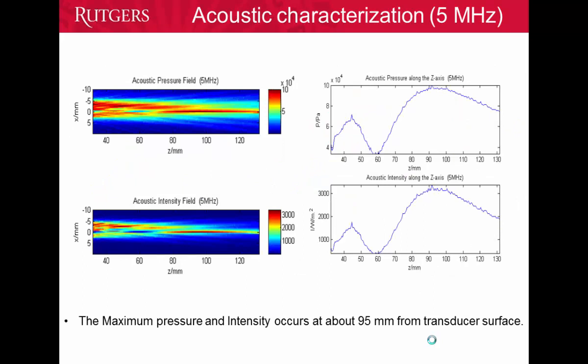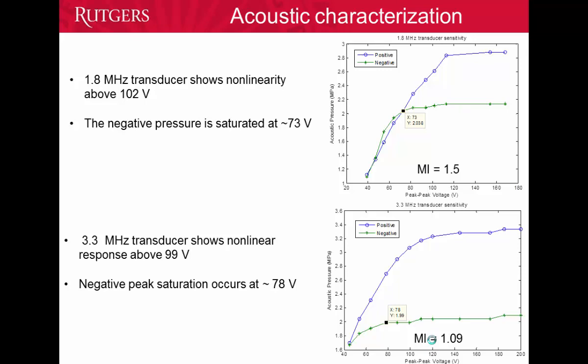Here you can see the two-dimensional distribution of acoustic pressure field and acoustic intensity aligned along the z-axis for the 5 megahertz transducer. The acoustic pressure and the intensity for this transducer reach the maximum at 95, which is the natural focal point because we didn't use any lenses. For the 1.8 megahertz transducer, you can see that the negative pressure is saturated at 73 volts, nonlinearity happened after 102 volts, and the mechanical index is 1.5. The 3.3 megahertz transducer has nonlinearity after 99 volts, and the negative peak saturation occurs at 78 volts with a mechanical index of 1.09.